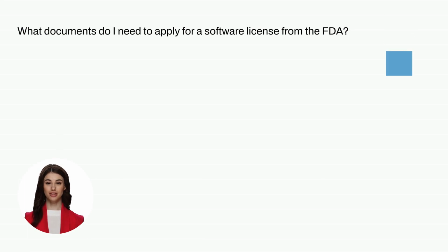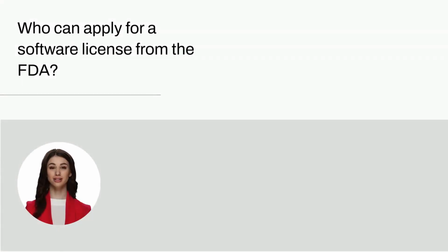documentation to apply for a software license with the FDA. For instance, if it's an implanted device, you'll need to include details on its design, operation, and safety and efficacy information. You simply need to submit information on the device's design and function if it's not an implanted device and doesn't need pre-market clearance or notice. It depends on your circumstances.